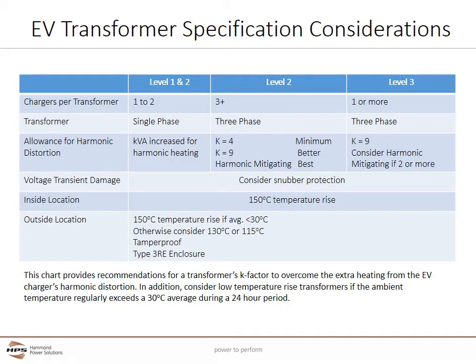The combined impact of multiple Level 1 and Level 2 charging points or just one Level 3 charger causes harmonic distortion levels, which can significantly impact a transformer's losses, temperature rise, and mean time between failure. The harmonic current of EV chargers is difficult to calculate. It varies with factors such as the initial battery state and the vehicle's charging profile. What is absolutely known is EV chargers will cause power quality problems. Single phase and auto transformers should be derated for this additional harmonic heating. Three phase transformers should be specified at a K equals 4 minimum for harmonic concerns.